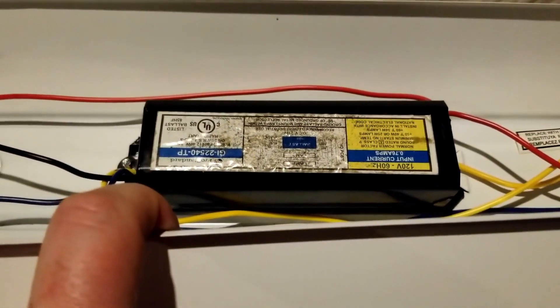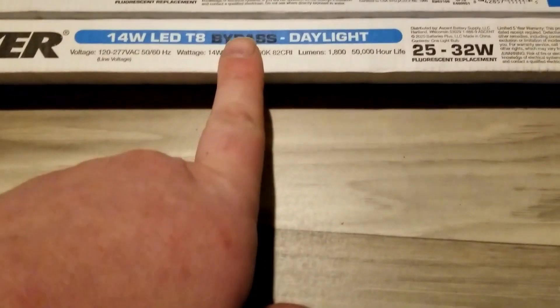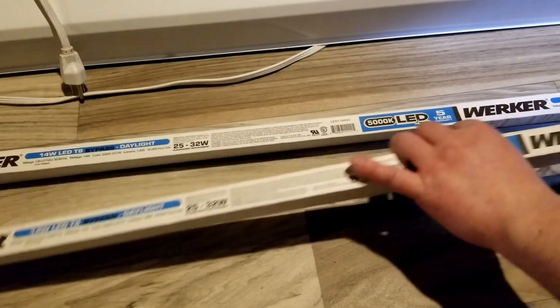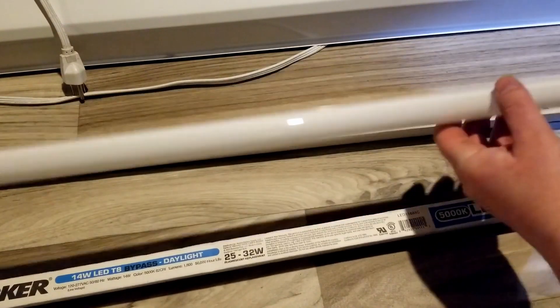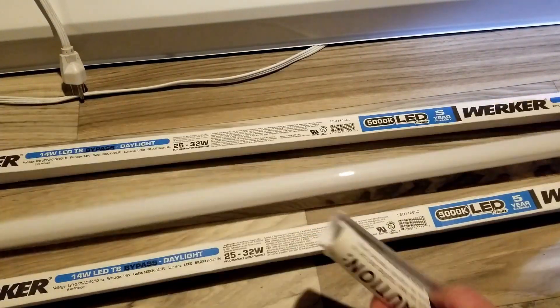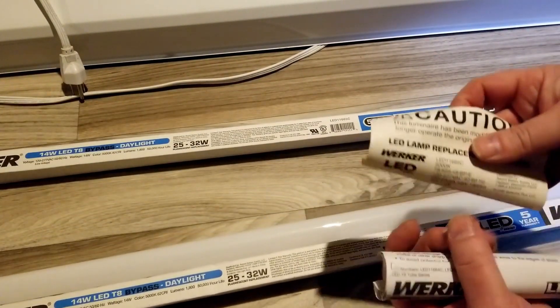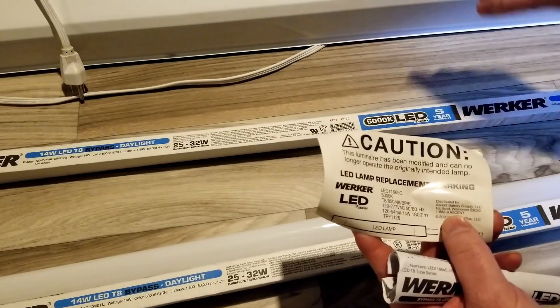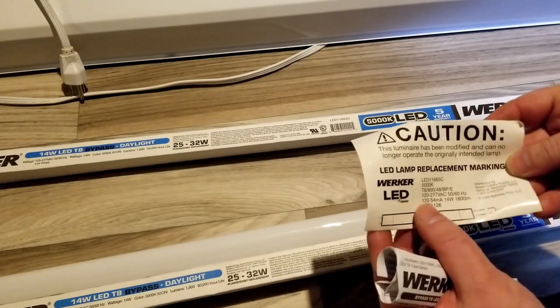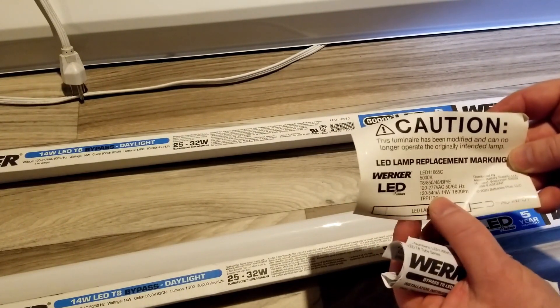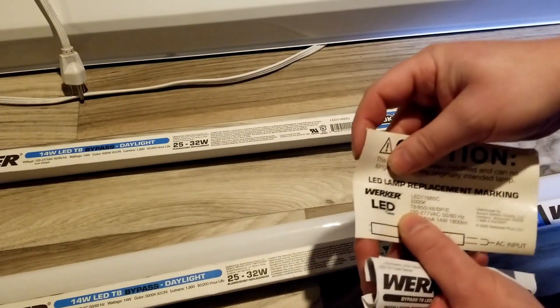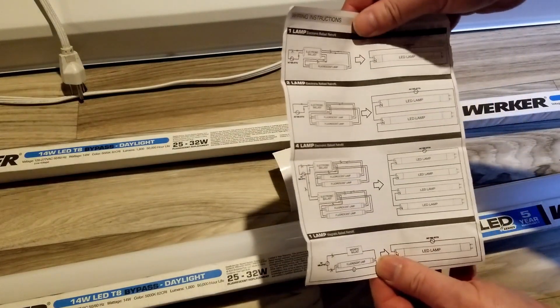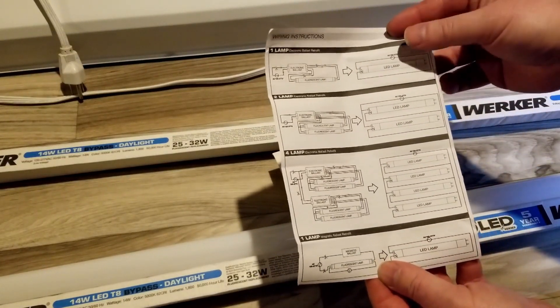But because this ballast is bad, we're getting the one that's a bypass. We're going to take that ballast out of there and run it straight to these bulbs. When we open one of these up, we get our bulb, some instructions, and a sticker. That sticker's got to go in the housing of the new one to let everybody know this has been modified for bypassing and for LEDs.